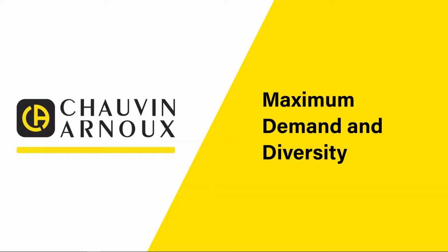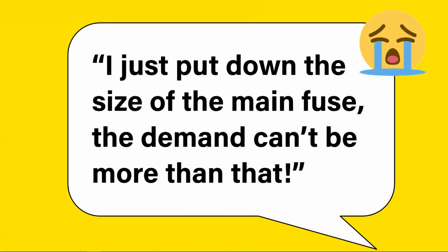Now in this section, we're going to take a closer look at maximum demand and diversity. Again, another thing that makes me sob. And I hear this a lot from electricians: I just put down the size of the main fuse, the demand can't be more than that. So this is a very common practice. Electricians, when they get a box on the electrical installation certificate that says maximum demand of the installation, they just say, oh, well, what's the rating of the fuse? 100 amps? Right, we'll put 100 amps down for maximum demand, and they don't give it any more thought than that. Now, we're just going to explore that logic a little bit with a little example.